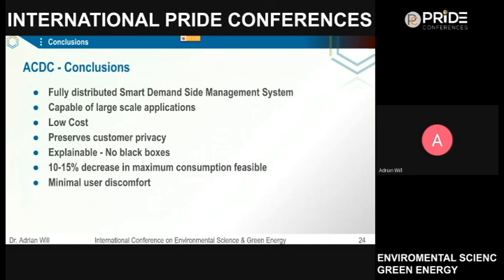And you can get to a 10-15% decrease in maximum consumption—it's feasible, it's doable, at least in Tucumán, because of the very large portion of air conditioning consumption. It's minimal user discomfort, both in that we don't make long stops, and you get fewer power outages. You don't need rotational load shedding, at least in the substation transformer where you're controlling enough clients. So the idea is to do as little rotational load shedding as possible.